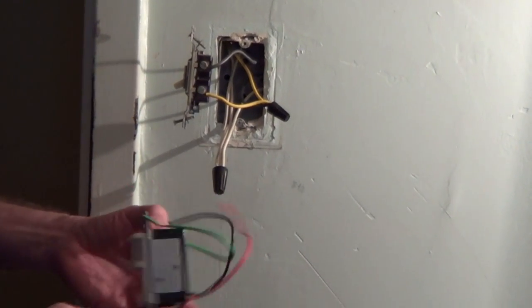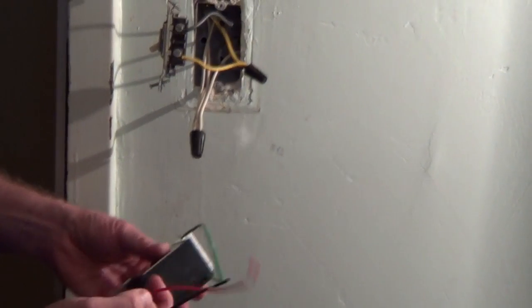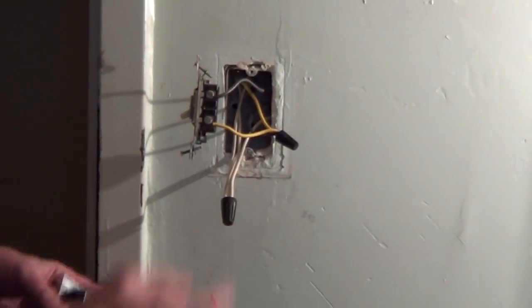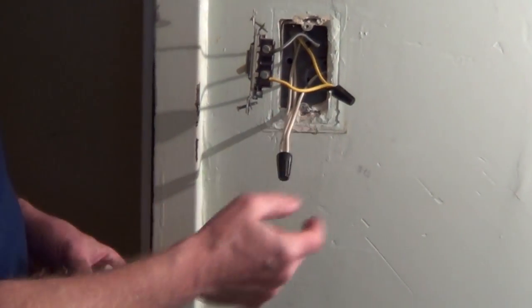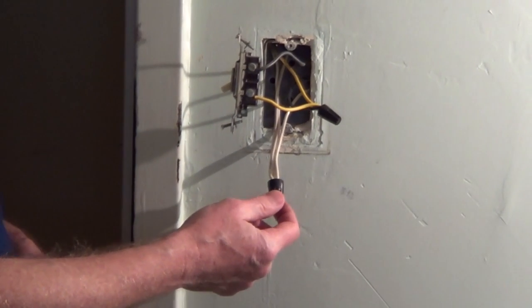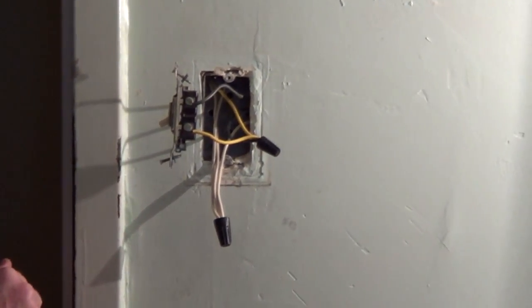In this case we have a single pole switch and we have a ground wire, we have two hot wires and a switch is just a break in the hot. So we have hot coming from the service panel and then going up to the lights. And if you have white wires in the box they're going to be twisted off with a wire connector. They're never connected to a switch.